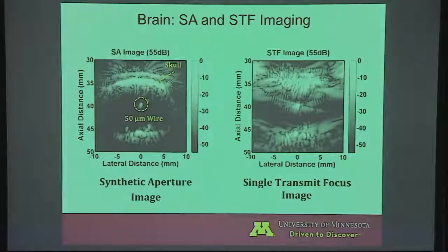This was an ex vivo experiment just to demonstrate what we do. For example, there is a 50 micron wire in here going through the brain tissue, and our DMUA would be imaging from this side. And typically we image in two modes. One we call synthetic aperture. This is all radar. Synthetic aperture techniques are radar-type imaging techniques that allow us to see more of the skull tissue and the base of the skull. And this is our wire target. This is a measure of the resolution of the system, which was demonstrated to be, as I mentioned, about 500 micron in the lateral direction and about 2 millimeter or less in the axial direction.